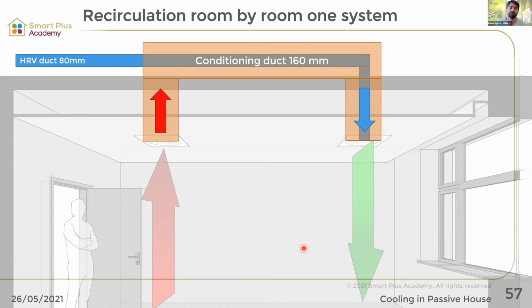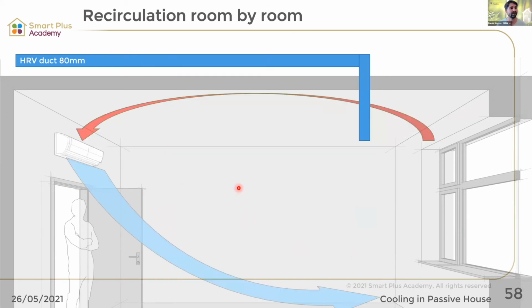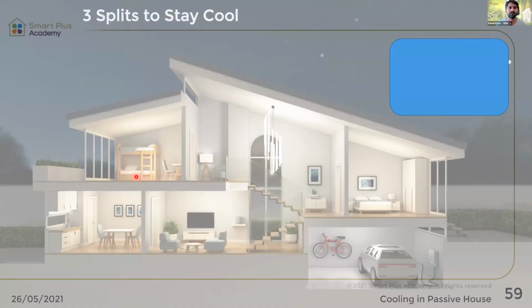The other option, my favorite one, is having your air supply via a heat recovery ventilation system, with your conditioning system completely separated. So if you're now speaking about split systems, my approach is normally three split systems for cooling, and for heating it would be the same. One in the biggest air volume of the building, so that we can handle the biggest volume of the building.